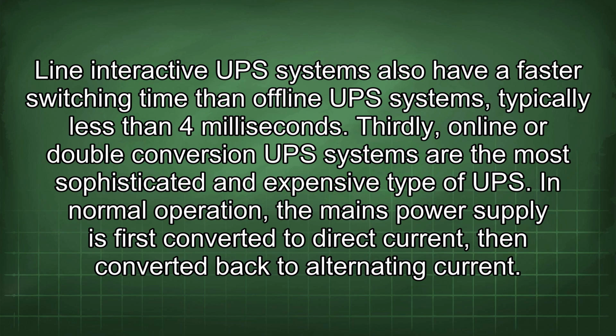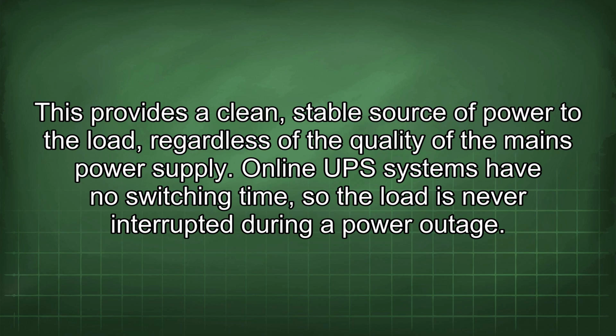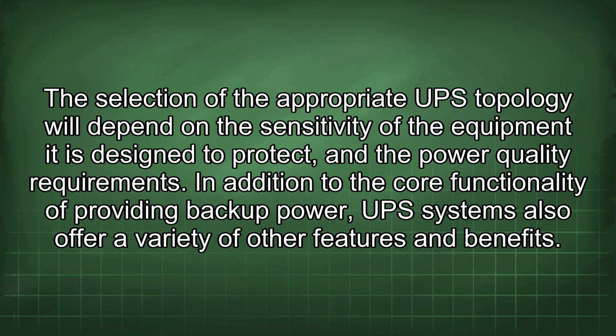Thirdly, online or double conversion UPS systems are the most sophisticated and expensive type of UPS. In normal operation, the mains power supply is first converted to direct current, then converted back to alternating current. This provides a clean, stable source of power to the load, regardless of the quality of the mains power supply. Online UPS systems have no switching time, so the load is never interrupted during a power outage. The selection of the appropriate UPS topology will depend on the sensitivity of the equipment it is designed to protect and the power quality requirements.